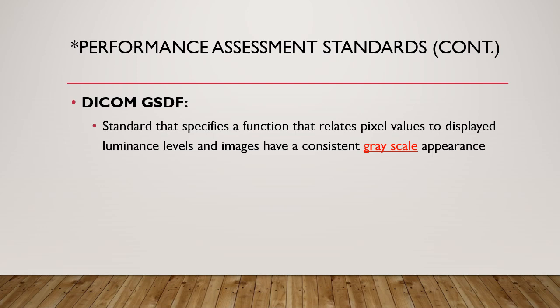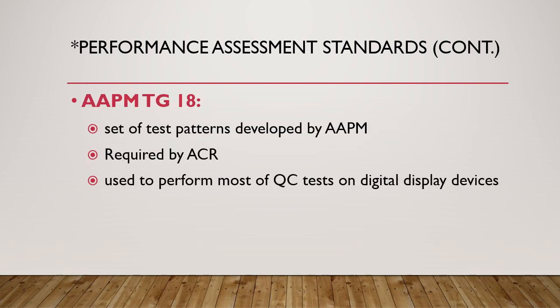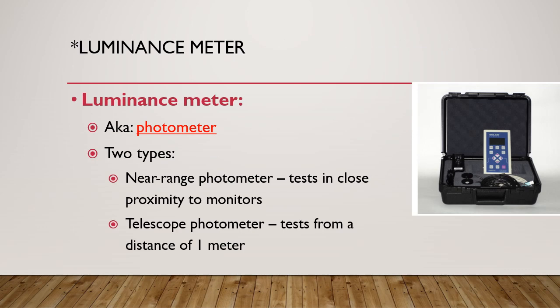DICOM GSDF is a standard that specifies a function that relates pixel values to displayed luminance levels, so images have a consistent grayscale appearance. AAPM TG18 are a series of test patterns developed by the AAPM. TG stands for task group, and 18 is just the number that they're on. They're required by the American College of Radiology, and they're used to perform most of the QC tests on digital display devices.